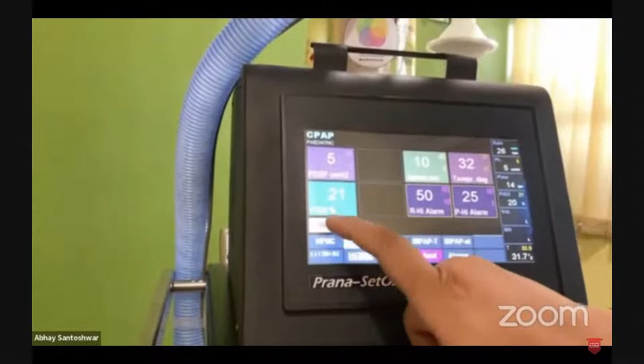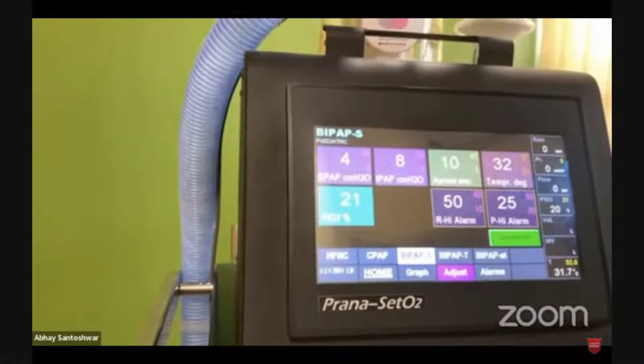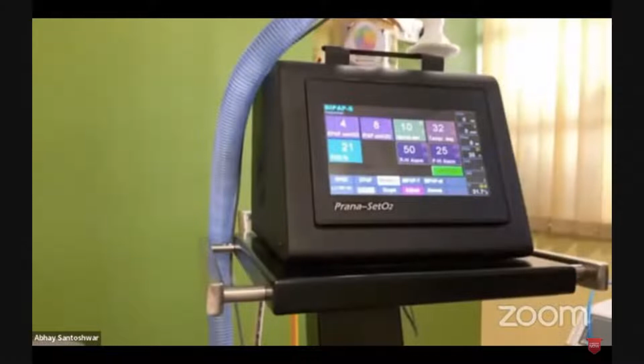Let's switch this off. Again, switching off a mode is as simple. You just stop it. And you go to the BiPAP S mode. In BiPAP S, one more parameter has got added, that is the IPAP pressure and the EPAP pressure. Rest of the other settings are still there. So let us start the BiPAP S.